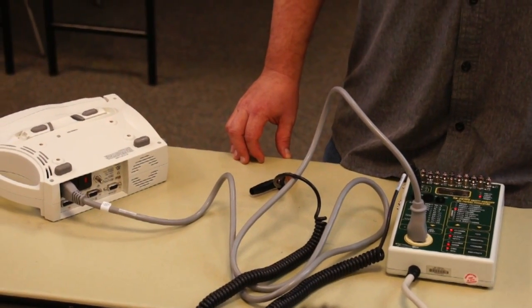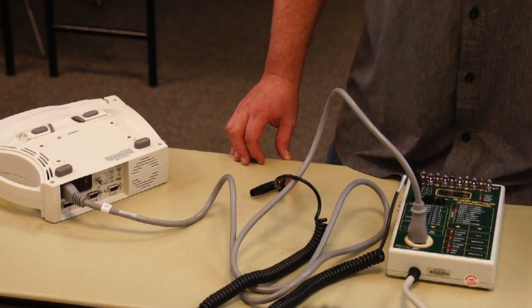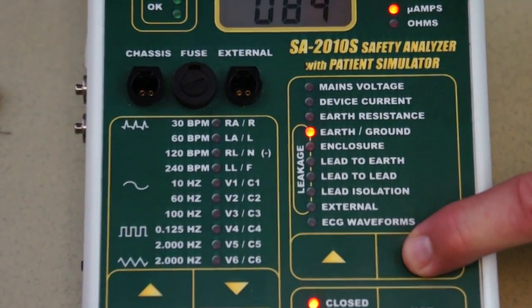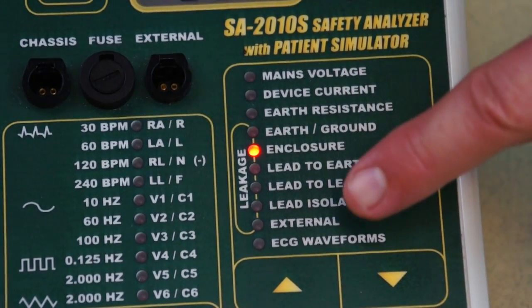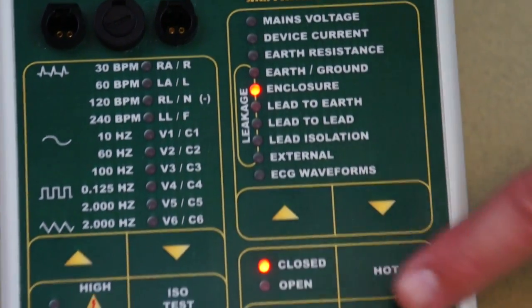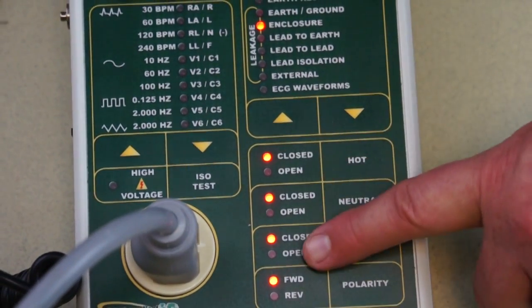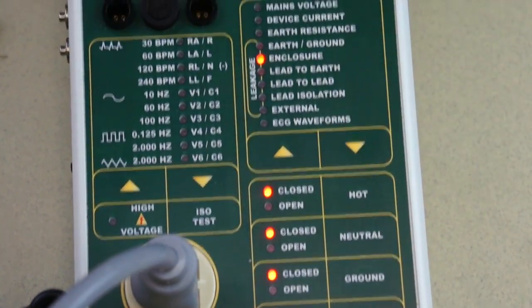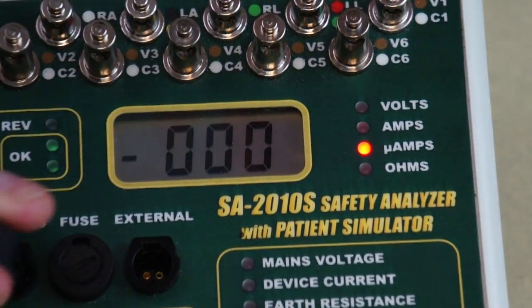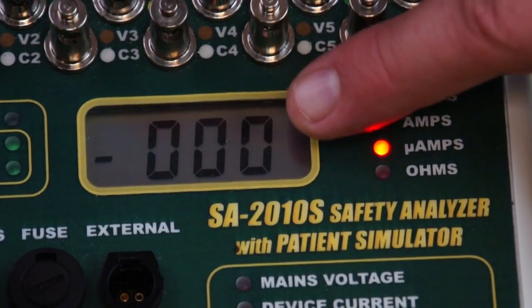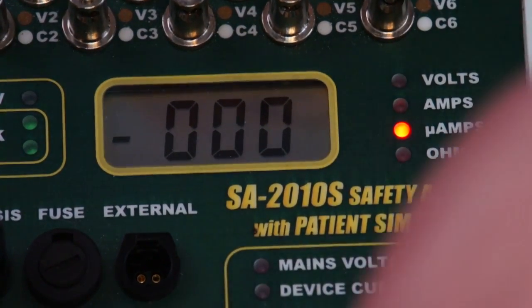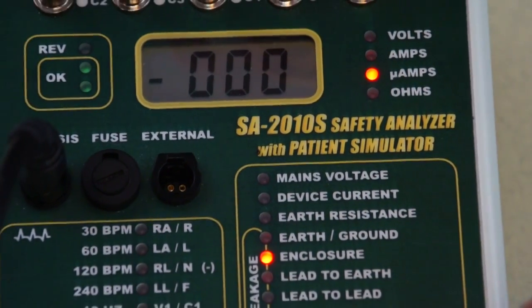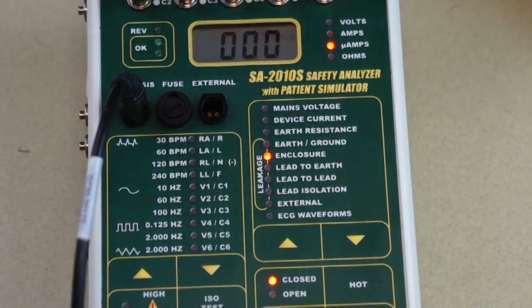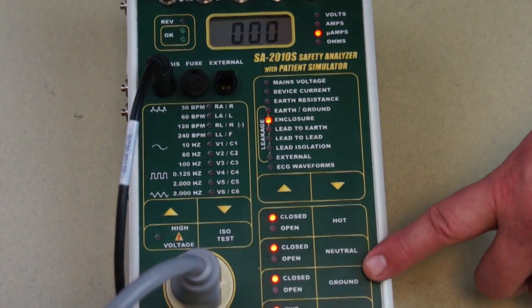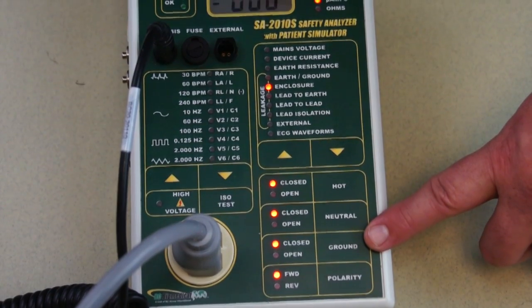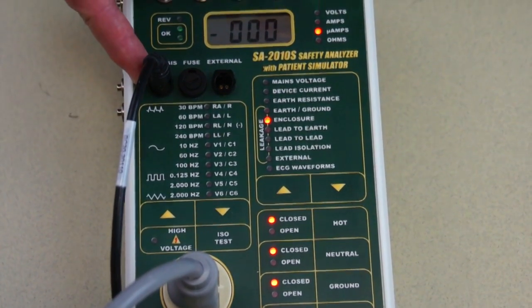Another way that we can do a leakage test is to change the mode of the analyzer to enclosure. Notice how all three inputs, ground, hot, and neutral, are all closed. Also notice that the value on the display is 0. This is because all of the leakage current is flowing through the ground wire on the test receptacle. In order to measure the leakage current, we need to open up the ground wire so that the leakage current will flow through the Kelvin lead and be measured.